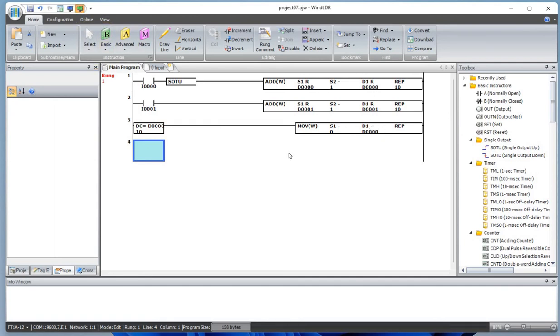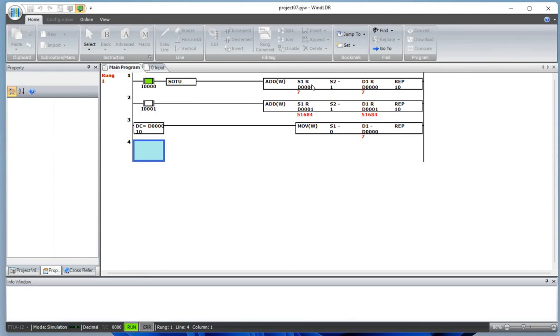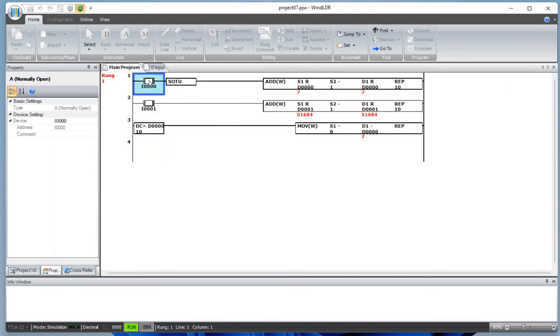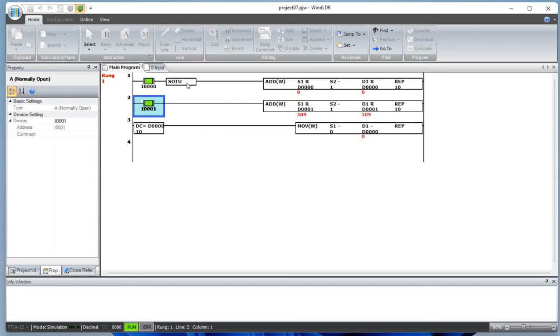Once the data register equals 10, zero will be moved to D0. Let's simulate: D0 is at 7, incrementing — 8, 9 — now when it hits 10, the data comparison is true and it sets D0 back to 0. So we've made a counter up to 10 using the ADD function with the single output up trigger.